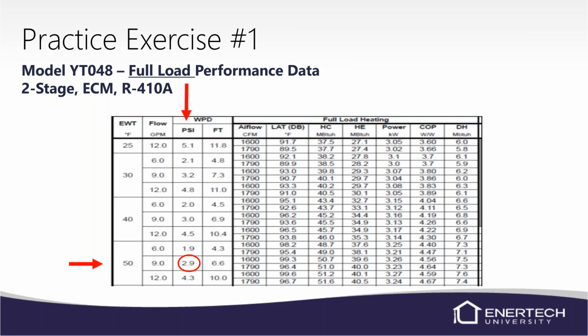A lot of times, if you've got a digital pressure gauge, it'll bounce a little bit, so you will have to kind of extrapolate the information anyway. As long as you're getting relatively close, you should be pretty good. But a 2.9-pound pressure drop at 50 degrees is 9 GPM. That's the minimum flow rate, which in turn is why you see a little bit higher temperature difference of roughly 9 degrees. Again, the slower you flow the water, the greater the temperature difference. It's in contact with the pipe longer, so it transfers more heat. That's why on an open loop you may see a 16, 17 degree temperature difference, where on a closed loop you'll see half of that because we're moving twice the amount of flow.